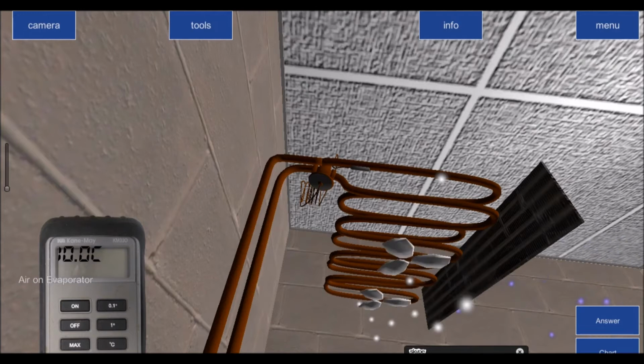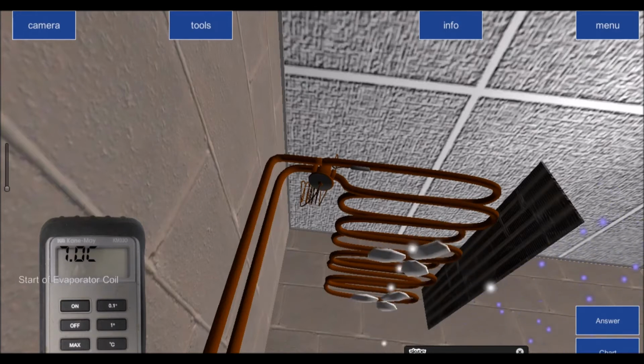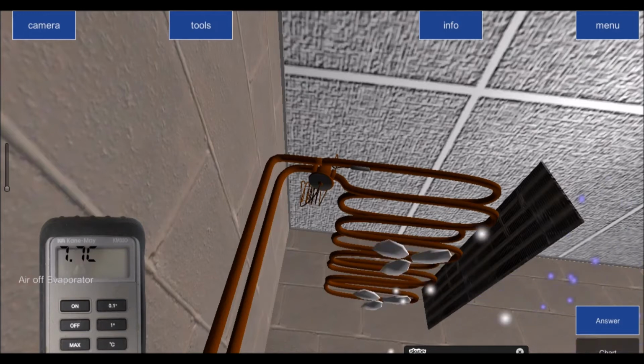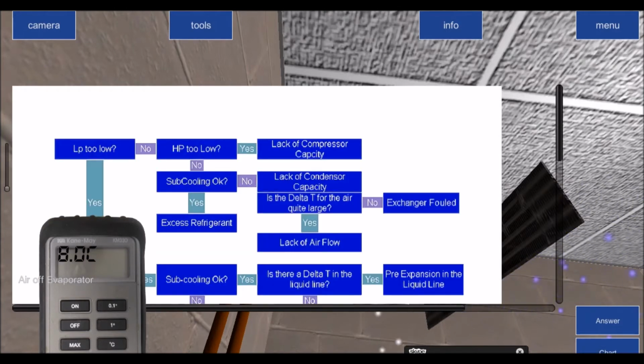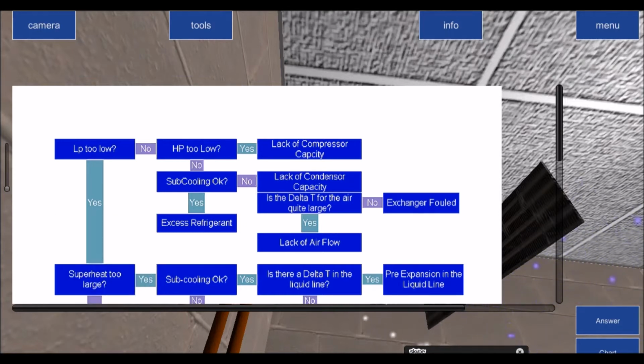In this particular case, I have an evaporating temperature of 7 degrees, which means that the evaporating temperature is actually higher than what I would expect it to be. Does that make sense? So, is it too low? The answer is no, it's not too low, because it's actually higher. Too low would be anything lower than 0 degrees. So -1, -2, -3, -4 would be too low an evaporating temperature. 6, 7, 8, 9, 10 degrees is higher than what we would expect.